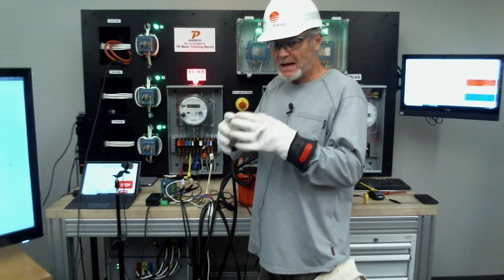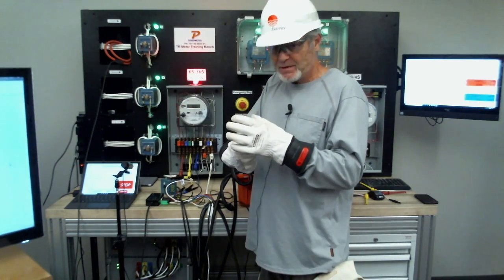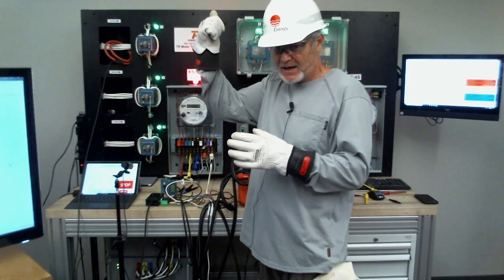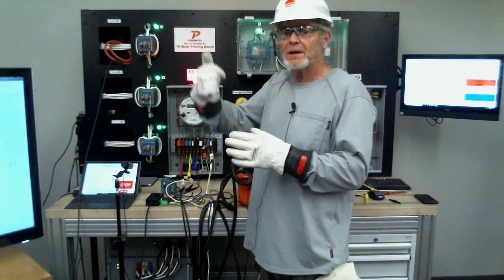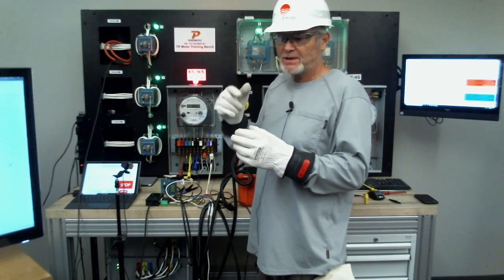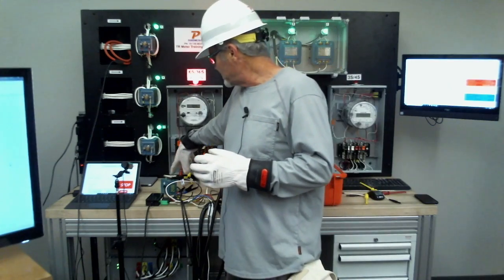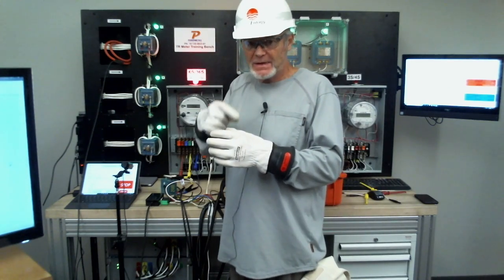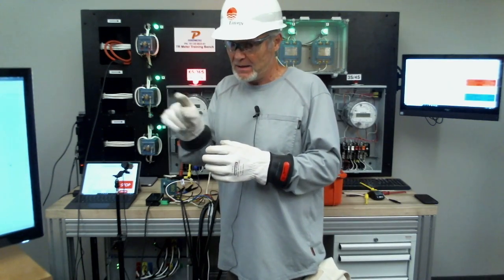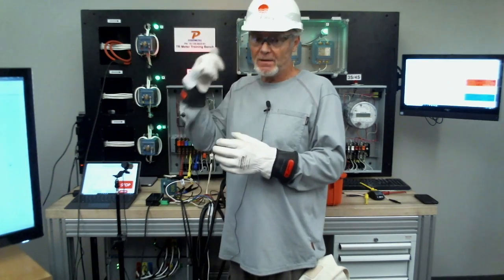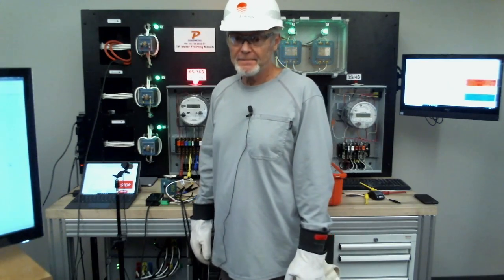So for the benchtop test, I'm pushing the current out of the dot side secondary, so that's where my white should be, because that's where the current's coming into the machine. Okay, so I should take my white connection, my in should be on the dot side of the secondary, right? Because that's where my current's coming into the machine, so I can read that secondary current. All right?